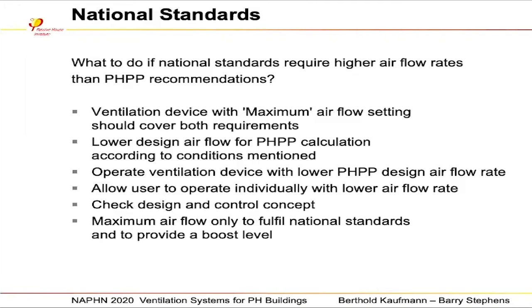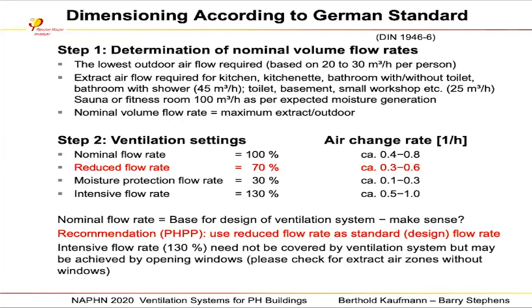Well, but on the next slide you can see again some numbers, and this is step one. You go for the standard and look what you need. And for passive house recommendation, you again have this 30 cubic meters per hour. But then you see on step two, what about the typical settings? And you see the nominal flow rate, 100%, is a little bit too high. This should be done only if it's really necessary. Normally, we recommend to have this so-called reduced airflow with 0.3 and 0.6. If people are out, you can go down to about 30% of the nominal airflow, and this is 0.1 to 0.3, so that it's not smelling if people come back to the apartment, and it's quite low, but it's a good compromise.